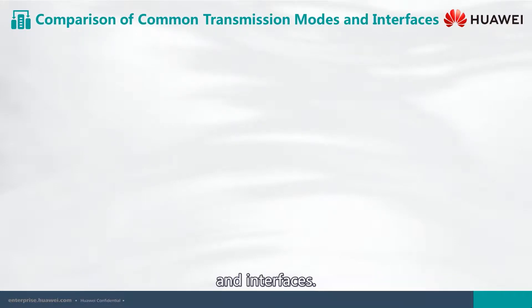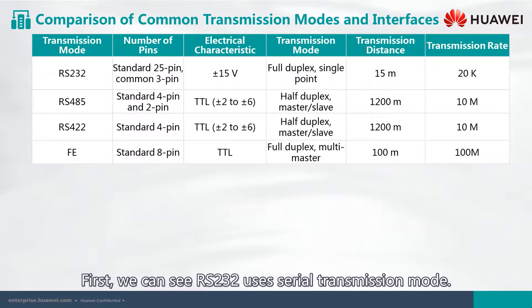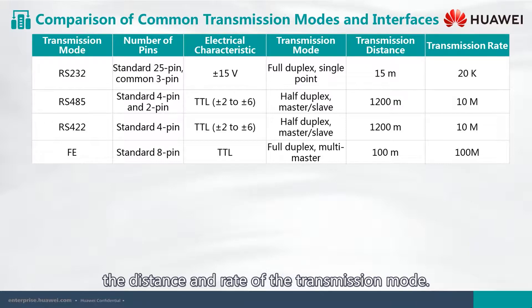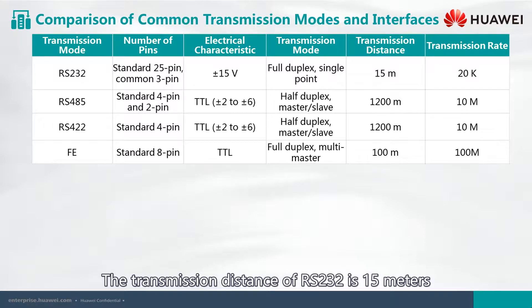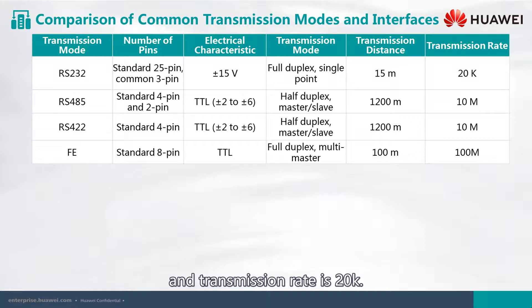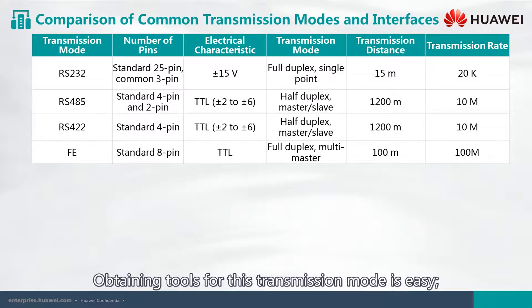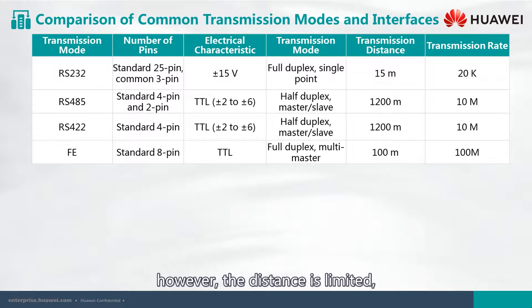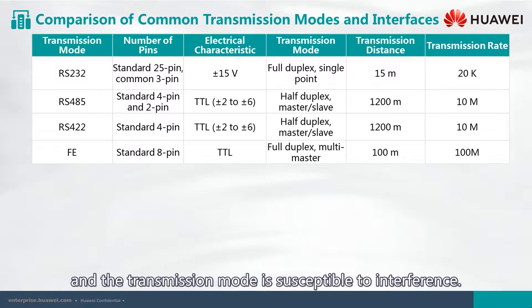Next, we will compare common transmission modes and interfaces. RS-232 uses serial transmission mode. We mainly focus on the distance and rate of the transmission mode. The transmission distance of RS-232 is 15 meters, and transmission rate is 20k. Obtaining tools for this transmission mode is easy. However, the distance is limited, networking is unavailable, and the transmission mode is susceptible to interference.